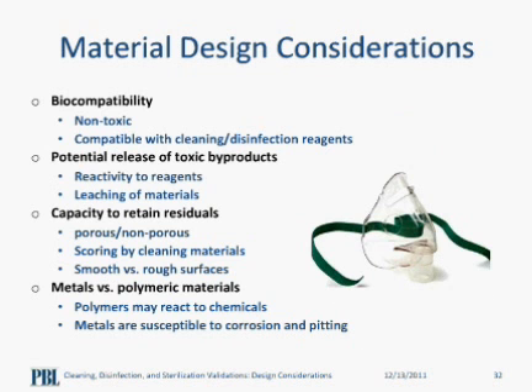Metals, as compared to polymeric materials, are more susceptible to corrosion, especially if they come in contact with bleach and hydrogen peroxide. Metals with coatings can be adversely affected by ultrasonic cleaning and also mechanical cleaning. These coatings can leach out from the device and may affect the user. Whereas polymers commonly react to chemicals, making them incompatible with some cleaning and disinfecting agents. It may result in discoloration or release of toxic byproducts as a result of the exposure.